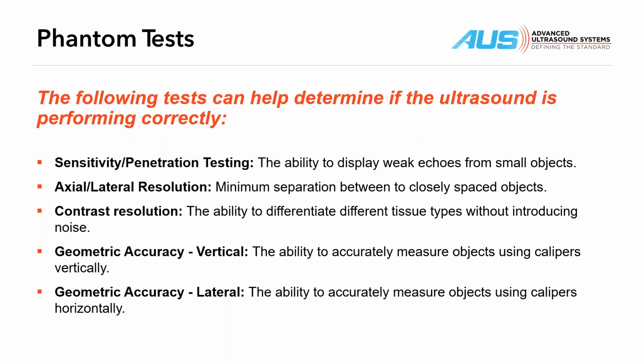Phantom tests, and these are the tests that we want to talk about in depth, if you will, that we want to perform with a phantom. Some of them are dictated by, for example, the American College of Radiology, and let's say the Intersocietal Accreditation for Cardiac Systems. Some of them aren't. I recommend doing these tests on every preventative maintenance. How you record them and report them will make the difference on whether you're ACR compliant, as an example.